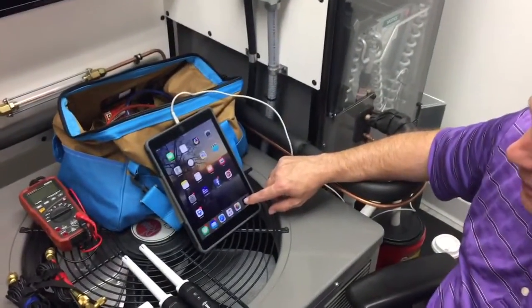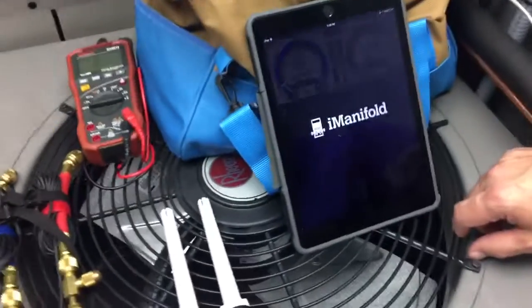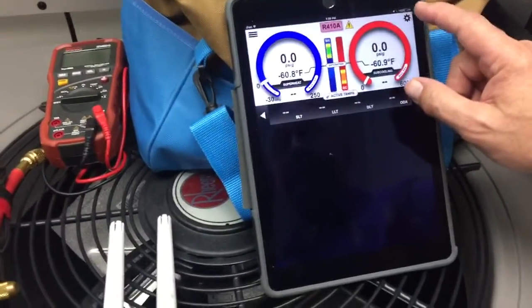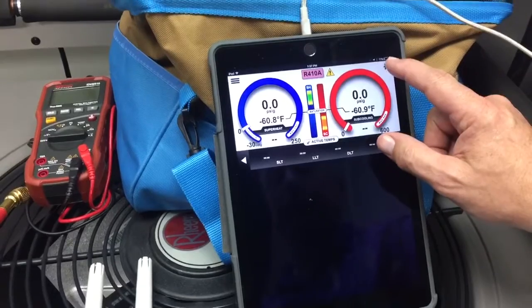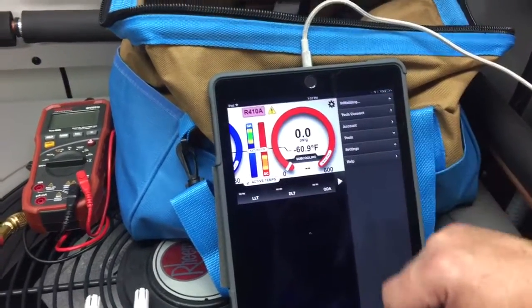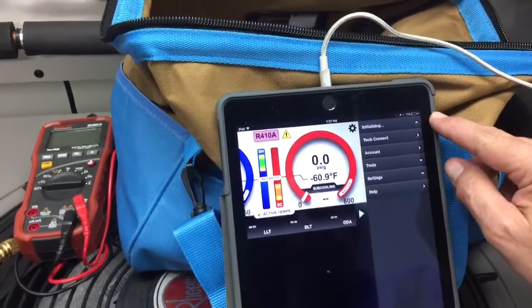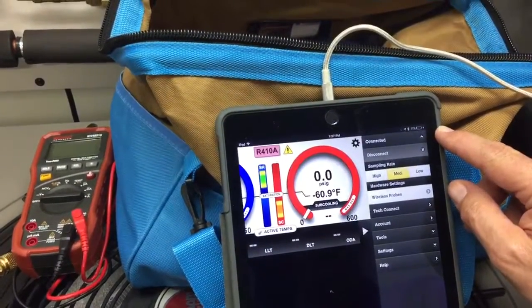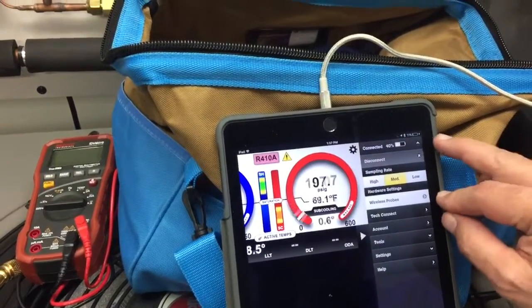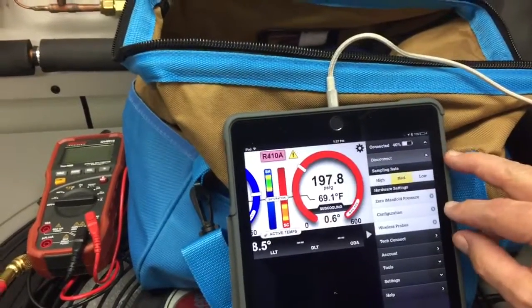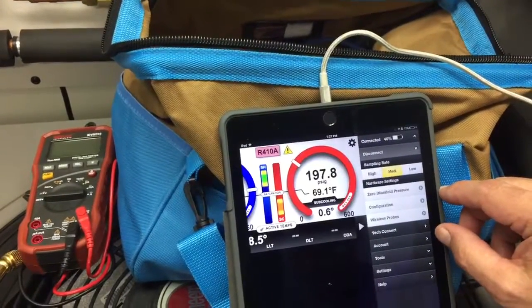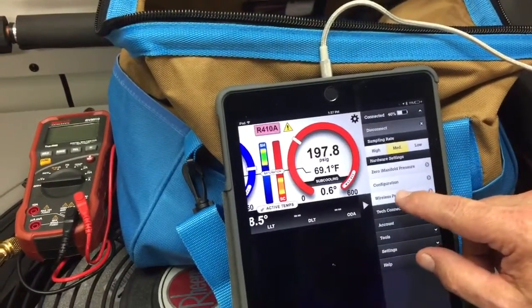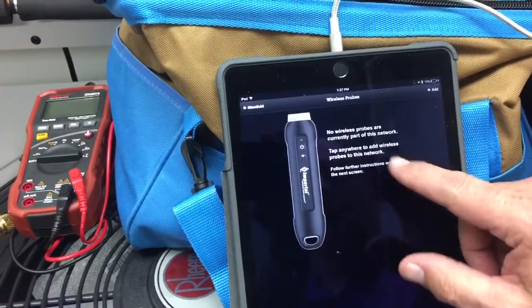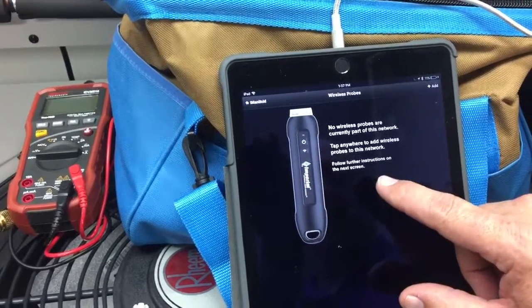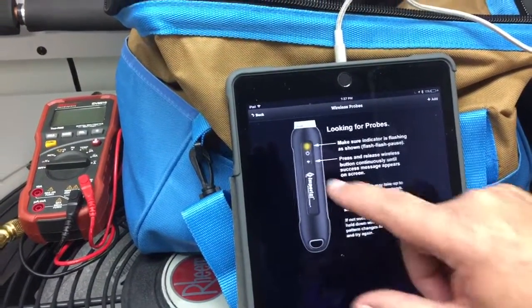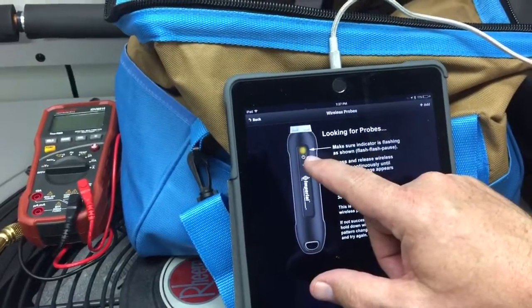The first thing we're going to do is tap on the iManifold icon. On an iOS device, there's no need to pair with Bluetooth, so we're just going to simply connect. You'll see it go through an initializing phase. You'll hear the iManifold beep, wireless probes will pop up, battery will start reporting in, and then we'll get a couple other menus. The first thing we want to do is tap on wireless probes. It says there are no wireless probes in this network, and we can tap anywhere on the screen to start adding. It's telling you it's looking for this double flash.